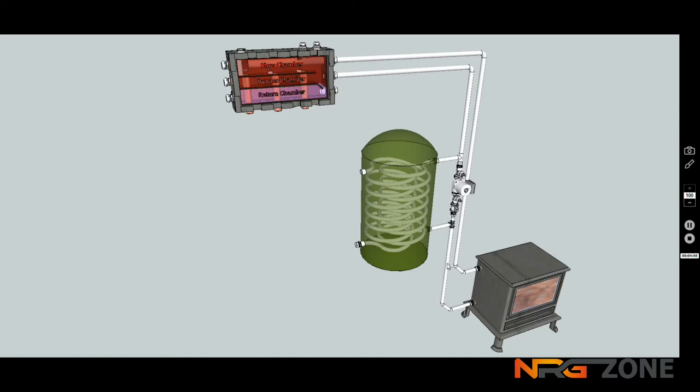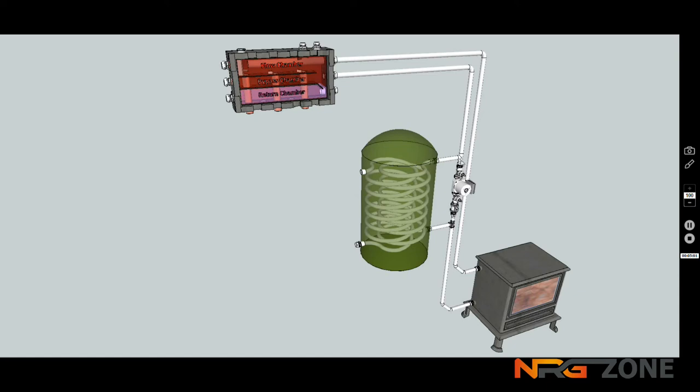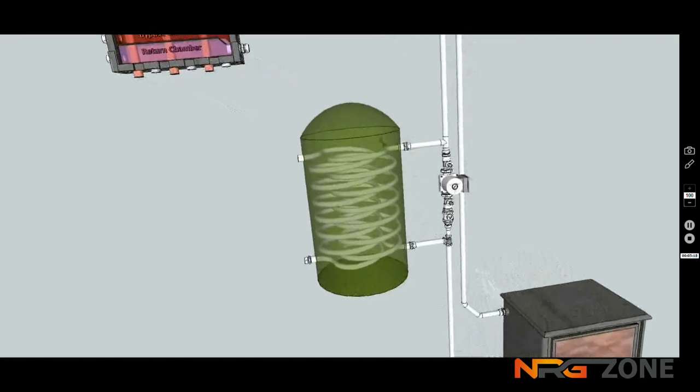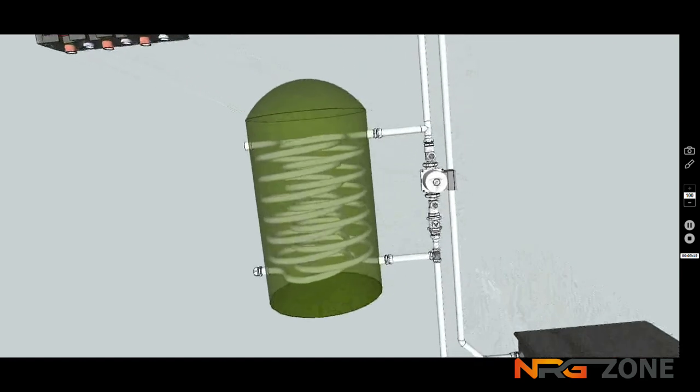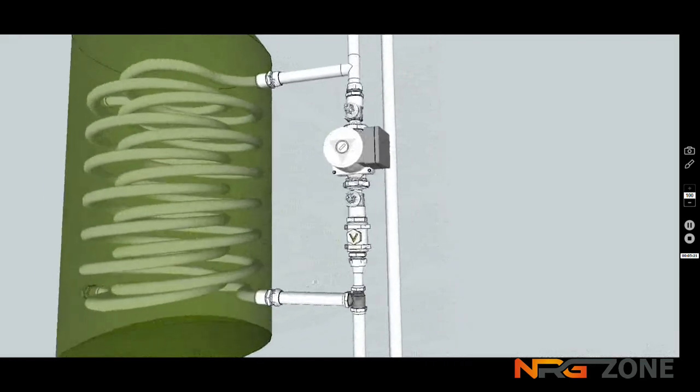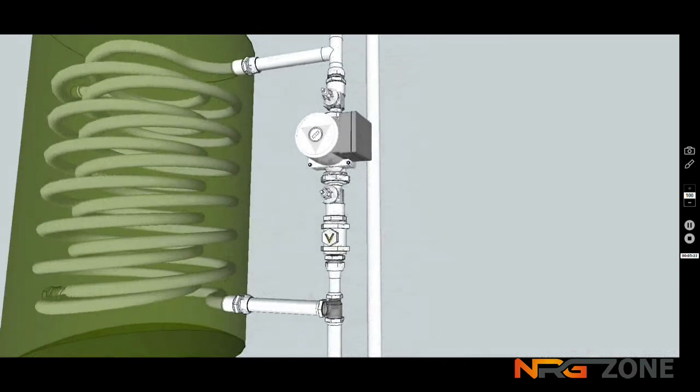If a thermostat detects that the return water is above 55 degrees, which typically is what stove manufacturers would require before any heat is drawn away to radiators or other zones, before this pump comes into operation, or any zone pump comes into operation, then the same water that arrived here that would be finding its way through the coil is now captured as well, and pulled through the pump for the first time, pushing open this non-return valve, and opening this path as opposed to the primary circuit through the cylinder, and then moves on down and into the injector T.